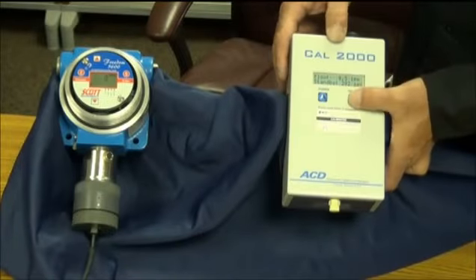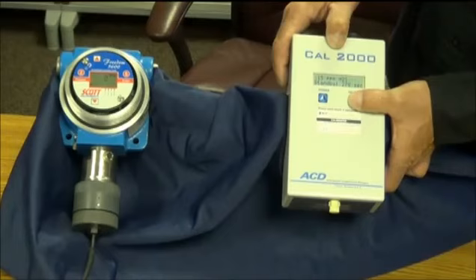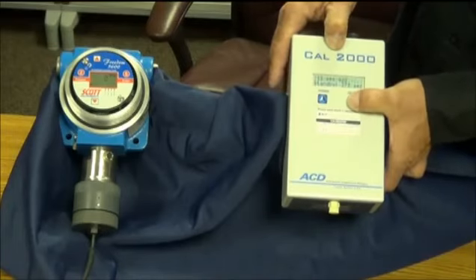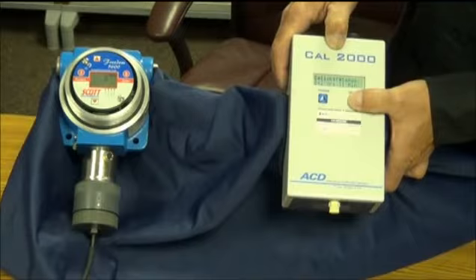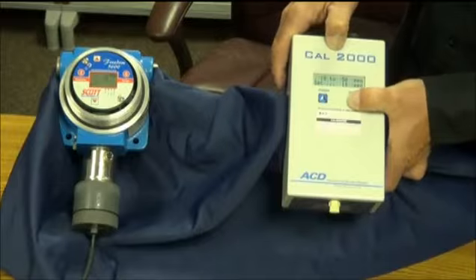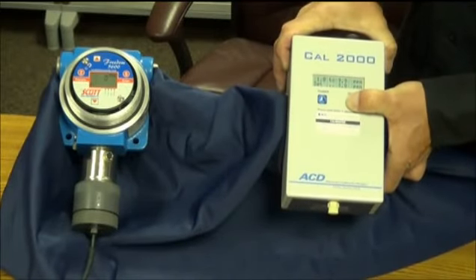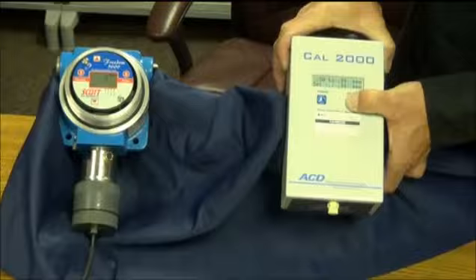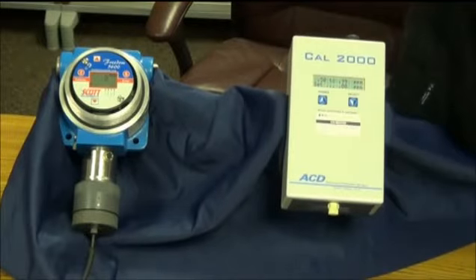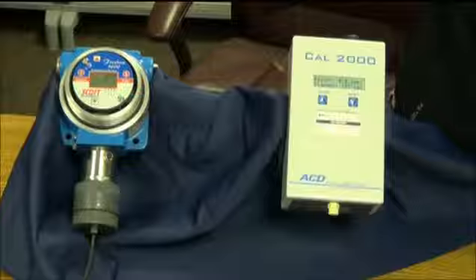First thing I want to do is zero this sensor. So I'm going to change this output to 0 ppm, and half a liter a minute is a fine flow rate. So I hit the select button. It goes through the data for me again, and when it shows output of 15 parts per million, I'm going to hit select here and go down to 0. Once we get to 0 ppm, I just release the select button, and it's going to stabilize. You're going to see it say stabilizing for 300 seconds, so there's a 5-minute countdown. After that countdown, we'll come back to you.